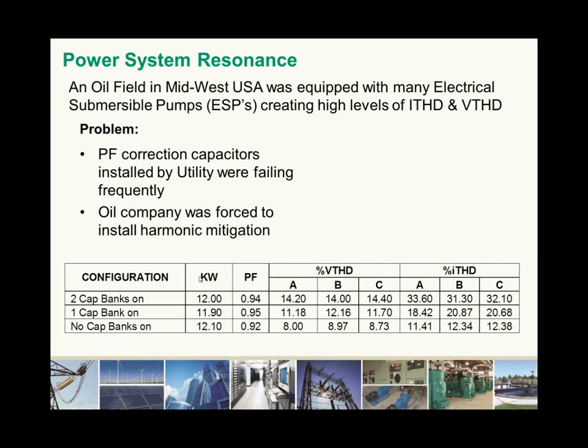The power factor was found to be low by the utility, so the utility insisted that the oil company install or pay for the installation of power factor correction capacitors at the utility substation. But those power factor correction capacitors actually made the situation worse, because they resonated with the harmonics generated by the electrical submersible pumps, and that drove the current distortion and voltage distortion up higher.